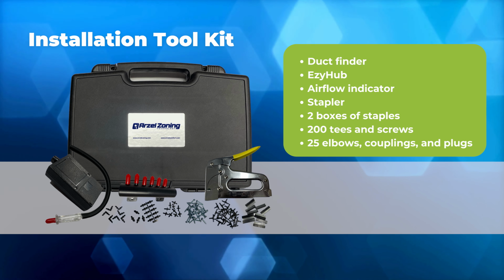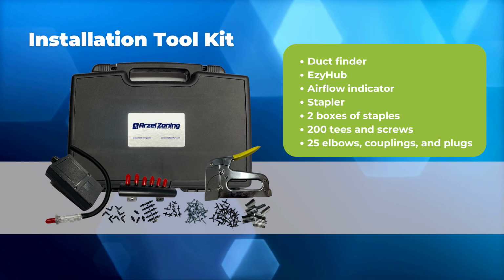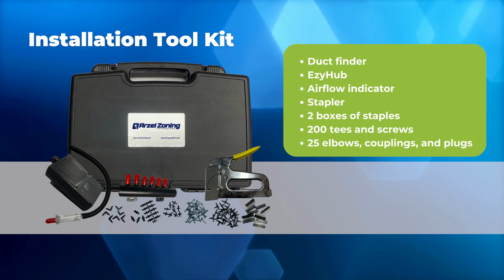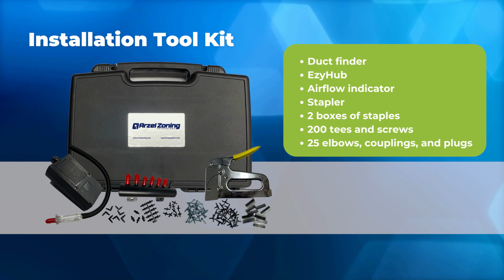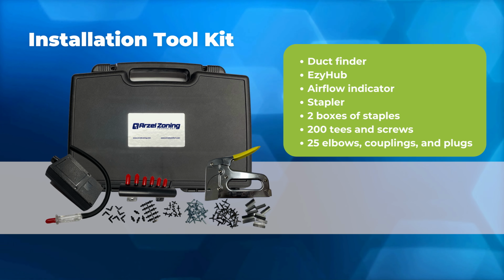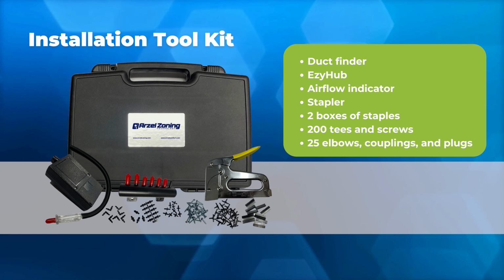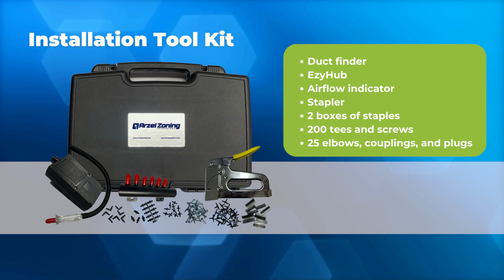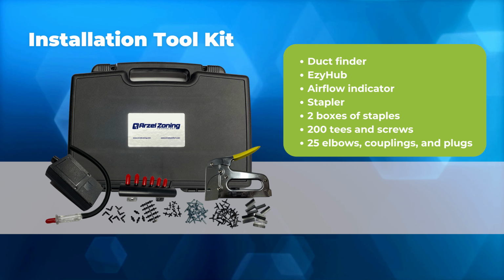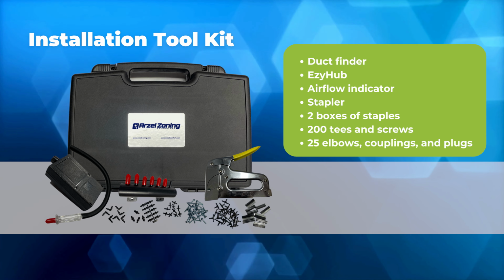And then we have our airflow indicator tool. If you guys have digital manometers on the truck, you're not going to really ever use this. All it really does is tell you if you have leaks in the damper system or something like that. We included it as kind of a last resort. Usually if you call tech support, we're going to ask you to have a manometer so that we actually can tell that the pump's good. Because with this device, it'll tell you if you've got a vacuum or pressure, but it doesn't tell you if it's adequate pressure or vacuum.